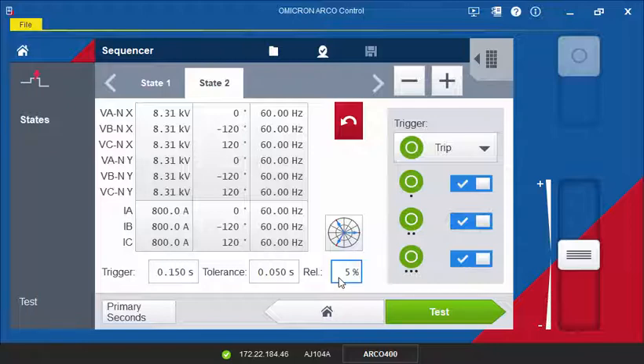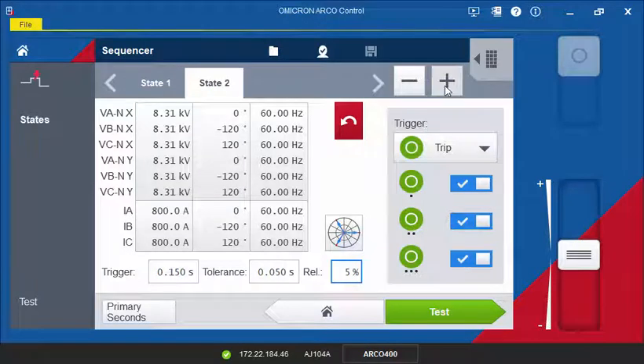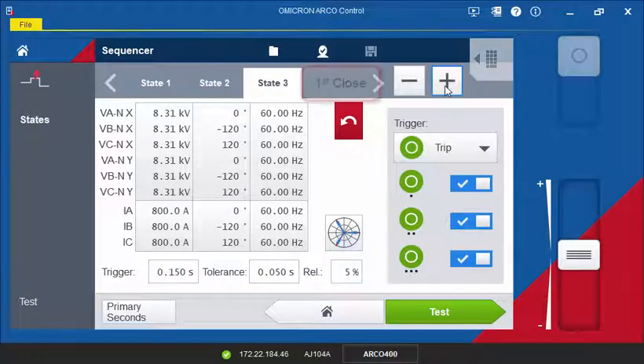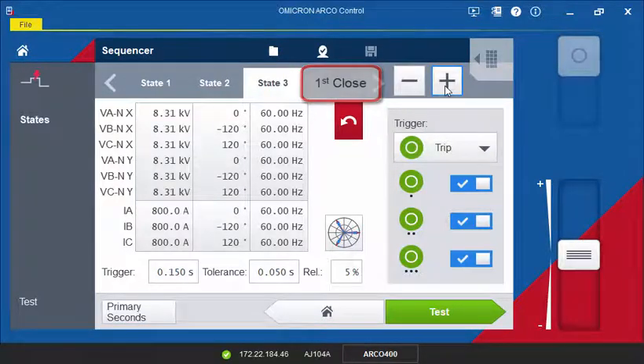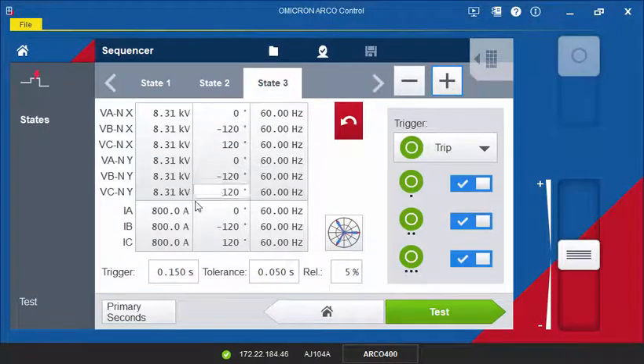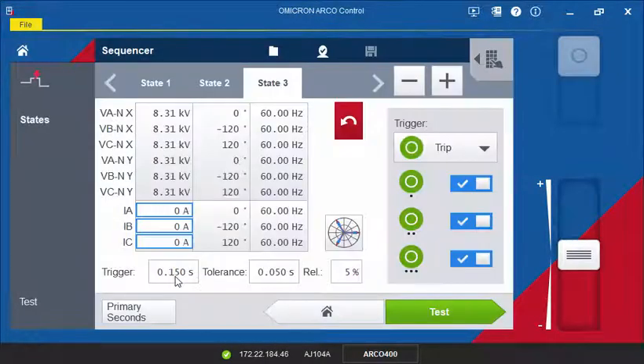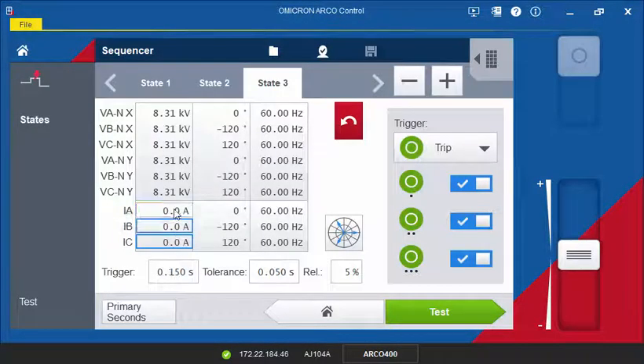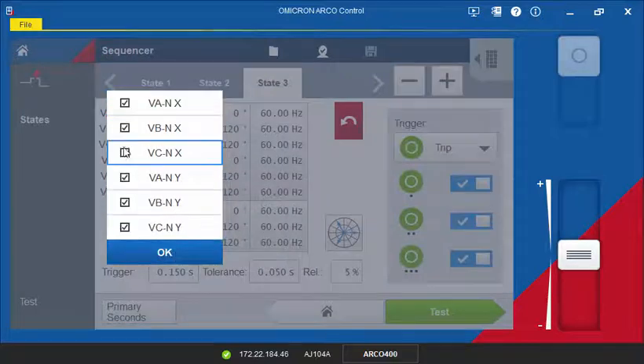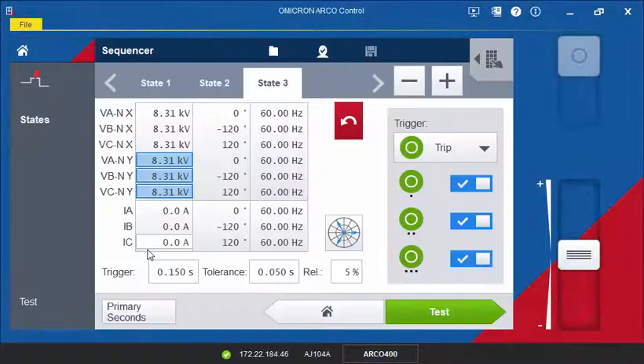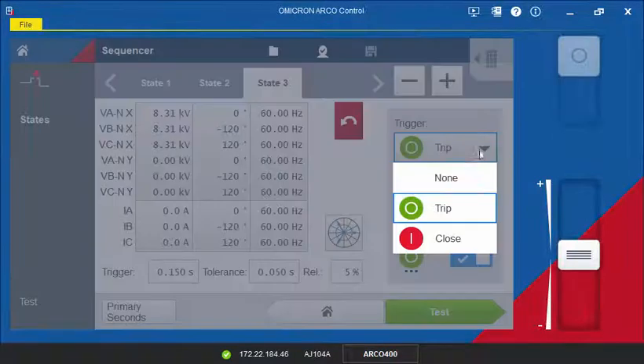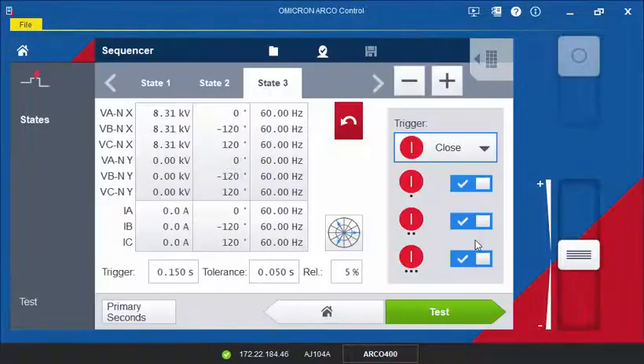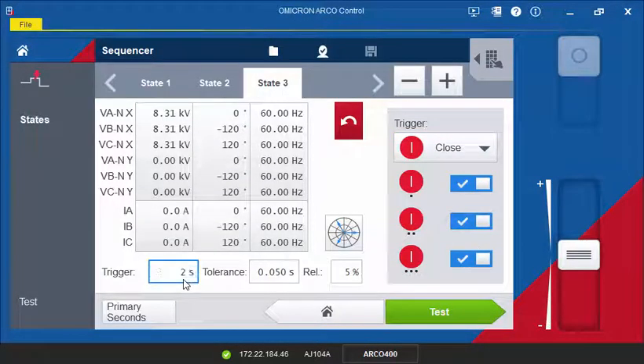Now we add a new state for the first reclosing cycle. We set the currents to zero and again we define a trigger, but this time we select the close signal. Enter the configured dead time for the trigger time.